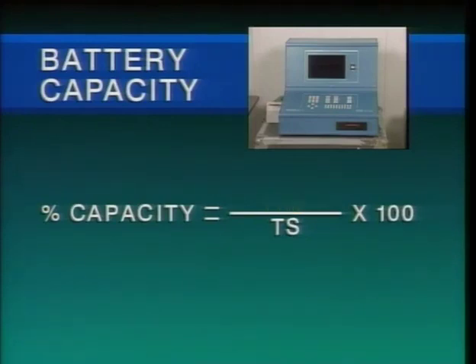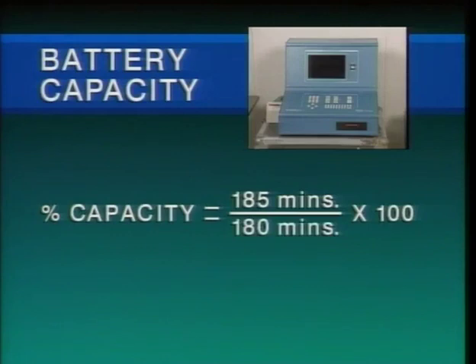In this example, 3 hours and 5 minutes, or 185 minutes. TS is the battery's rated time for discharging to the minimum acceptable voltage. In this example, the rated time is 3 hours, or 180 minutes. 185 divided by 180 is 1.03. 1.03 times 100 is 103. So the capacity of the battery is 103%. IEEE Standard 450 recommends that a battery be replaced when its capacity drops below 80%.